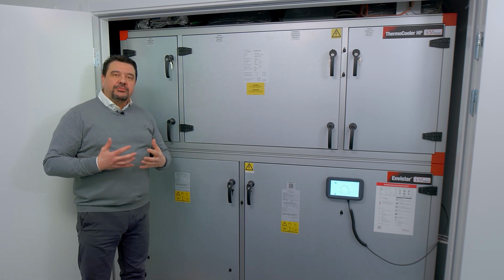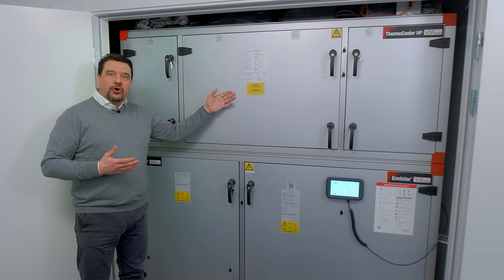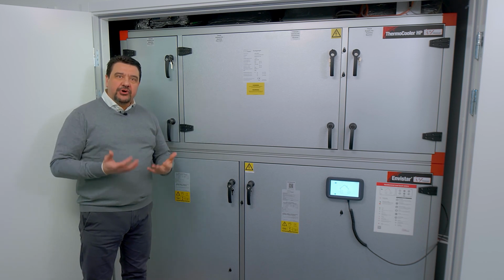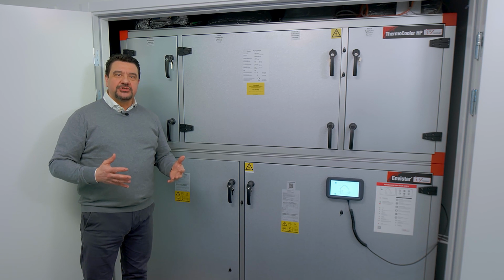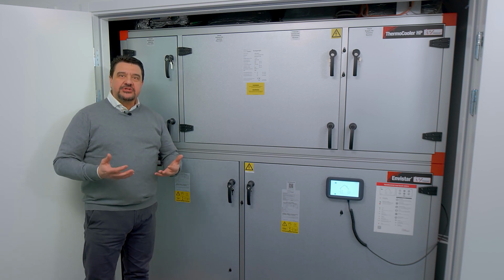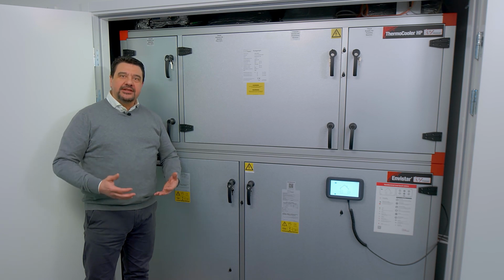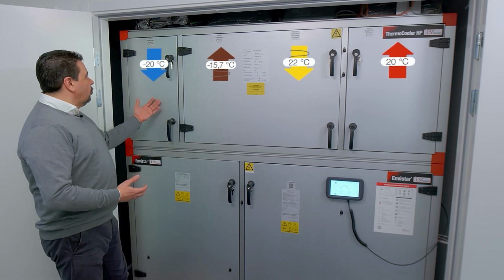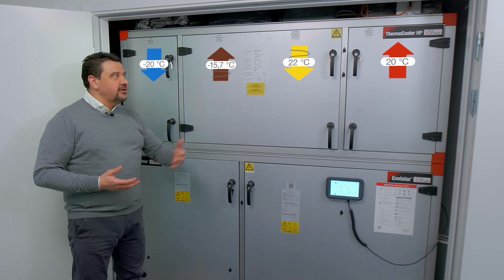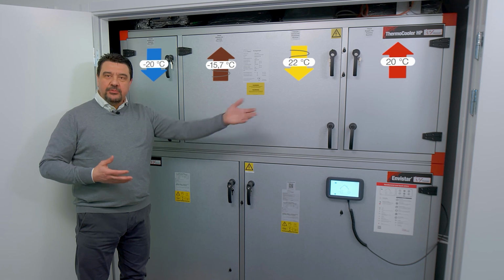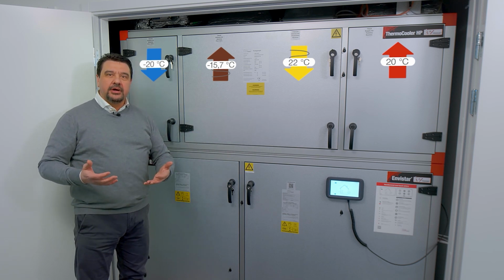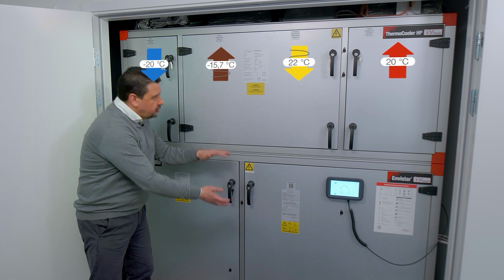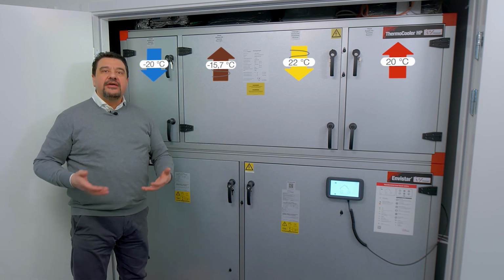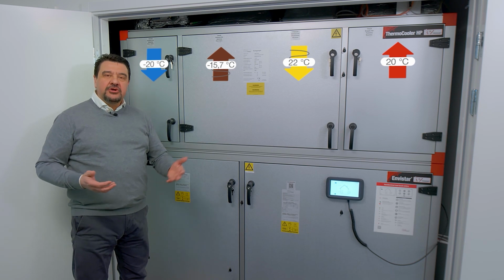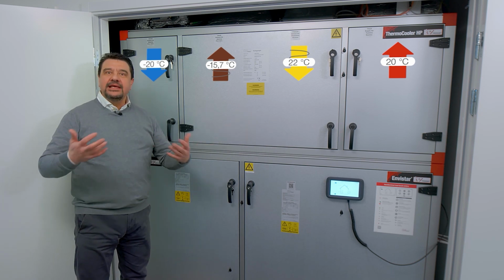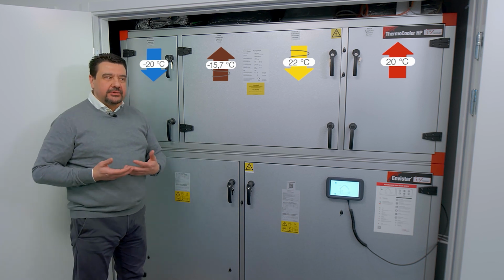And we have combined our top units with our latest innovation, ThermoCooler HP, a stepless reversible heat pump, completely without defrosting needs. Which means that we can heat the supply air wintertime and we can cool it down summertime. Say we have a cold winter day of -20 degrees. We have 22 degrees in the extract and we still want to blow in 20 degrees to the room. And by combining a high efficient rotor with a heat pump, we can have an energy recovery of up to 90%. So we can blow in 20 degrees completely without heating coils or pipe systems.